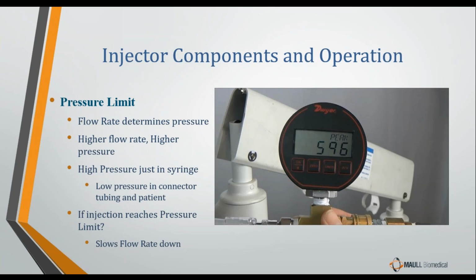And that is the reason that sometimes the operator is not programming the injection properly, if they don't have a complete understanding of pressure limiting. If they are supposed to set this system up and shoot this injection at a flow rate of 5 milliliters per second, and we should set this pressure limit to 600 psi, the operator's thinking, man, 600 psi, that is 600 pounds, and the tip of this catheter is going in the patient's right atrium, inside their heart. Boy, that's an awful lot of pressure. We can't put 600 psi in the patient's heart. So what they'll do is they'll dial it down to 200 psi, 300 psi, some lower pressure, like that would be just fine in the patient's heart.